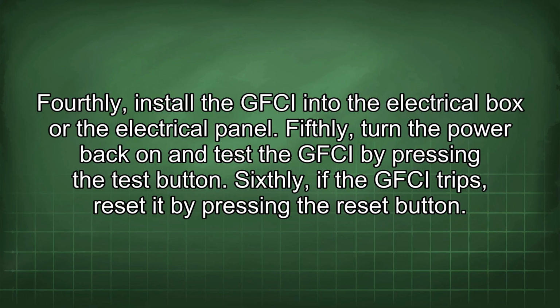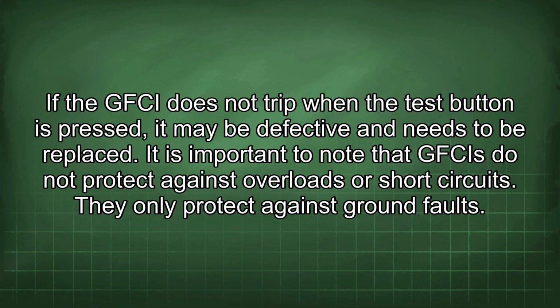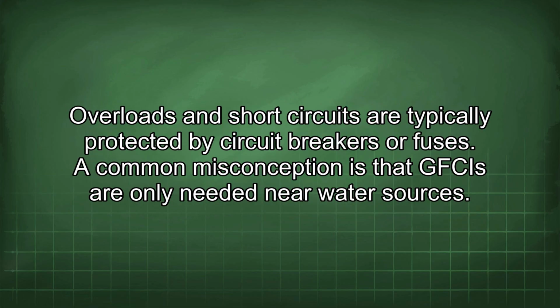Fifthly, turn the power back on and test the GFCI by pressing the test button. Sixthly, if the GFCI trips, reset it by pressing the reset button. If the GFCI does not trip when the test button is pressed, it may be defective and needs to be replaced. It is important to note that GFCIs do not protect against overloads or short circuits. They only protect against ground faults. Overloads and short circuits are typically protected by circuit breakers or fuses.